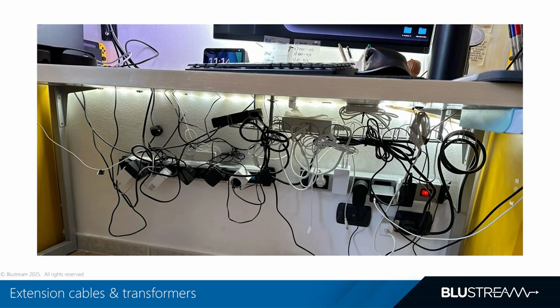Now that gap is exactly where our new low voltage PDU fits. Instead of scattering supplies and guesswork, you get a single, organized hub for small device power and per device management. The goals here are simple. Cleaner installs, so no more wall wart jungle, better airflow, and it's easier to service. You've got better resilience, so protection and orderly sequenced recovery after outages, and smarter operations, so we can do things like remote reboots, scheduling for off hours, and visibility into consumption so you can diagnose issues quickly and plan capacity.